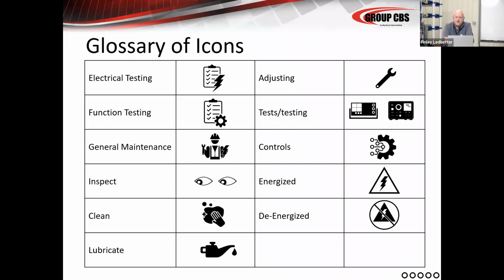And just to give you an idea of what we're talking about, obviously these little eyeballs here is a human actually doing an inspection, because there's no way you can get away from that. That's really the best thing we can do for this equipment: operate it, clean it, and put human eyes on it. You can't always do that. You can't always get to the equipment. You can't always get it out when you want to. Lots of times operating conditions in hospitals and data centers and lots of facilities won't allow you to get the equipment out on regular intervals.